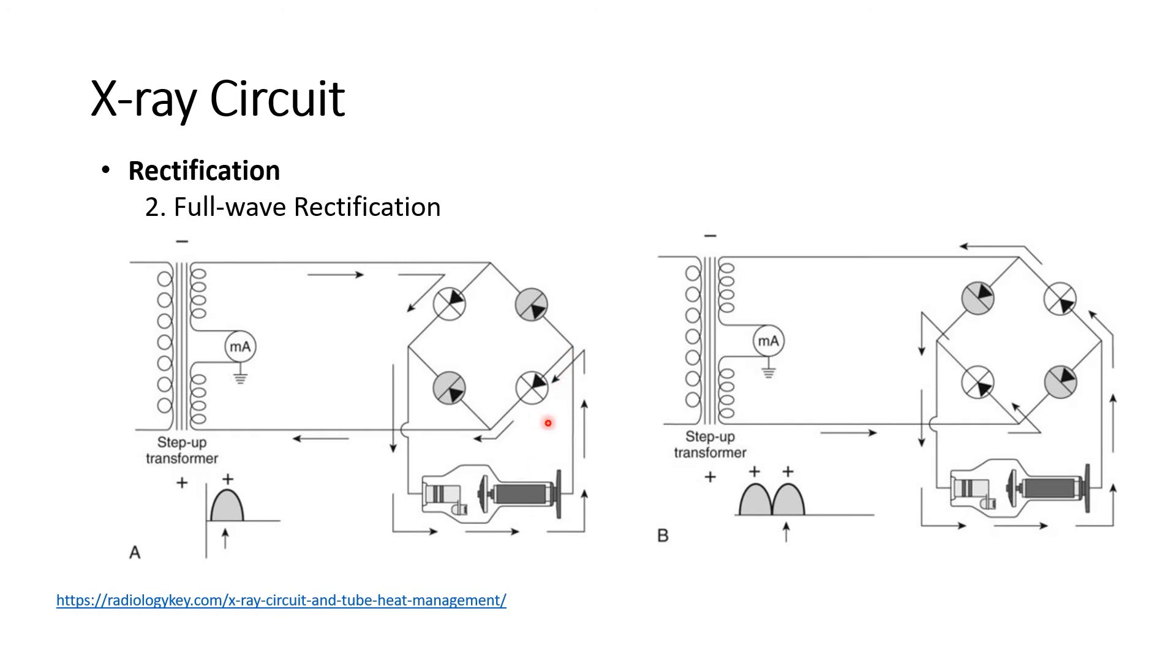Current can be redirected so that it will only flow in the same direction throughout the cycle, thus producing a DC. This process is full wave rectification wherein the entire electric cycle is used for X-ray production. In this case, the X-ray output will occur at 120 Hz compared to the 60 Hz for half wave rectification, thus doubling the X-ray output.